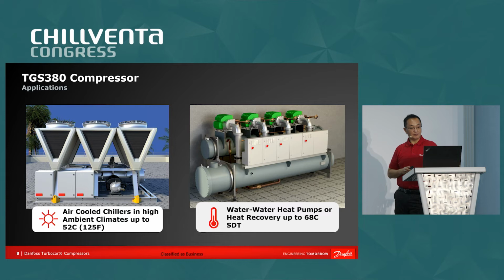So just to give you some visual representation of some of the things that this can achieve. Because of the high pressure ratio capabilities of about 5.7 on this compressor, it's very suitable for operating in air-cooled chiller applications, especially in a high ambient climate, such as the Middle East. It's capable of operating without any risk of faults or alarms, and it can operate up to 52 C ambient temperature.